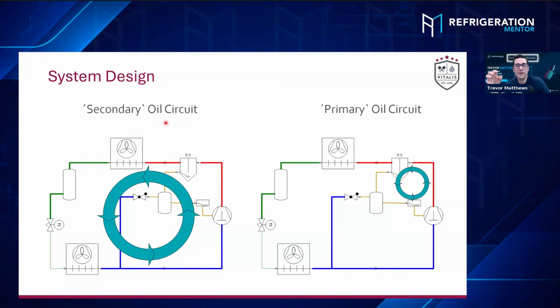It's not ideal because we want to keep everything at the rack. This is once again no different than an HFC or synthetic system. We want to keep the oil there in these multiple or parallel rack applications. This is a booster configuration. But the more oil that travels out in the system, the more oil we would have to add, and we can't just add and remove oil. This is what's happening out there. People will go out and add 5 gallons and say, oh, we got oil coming back now. And it works for a few days. And then all of a sudden there's no more oil again.